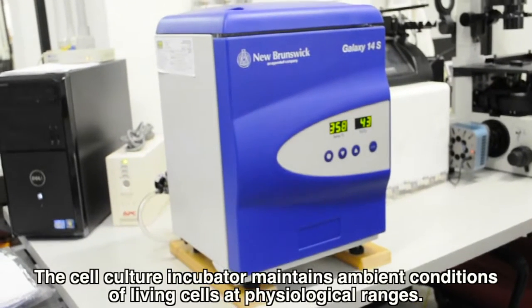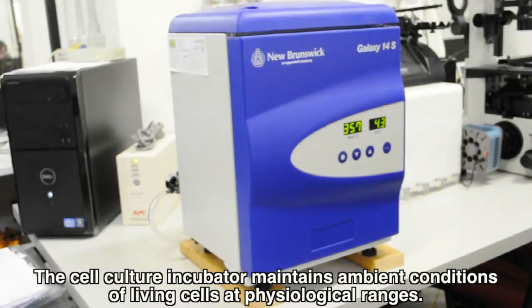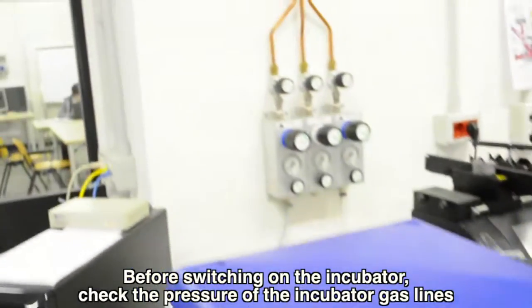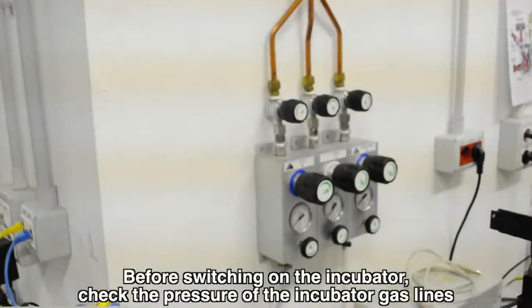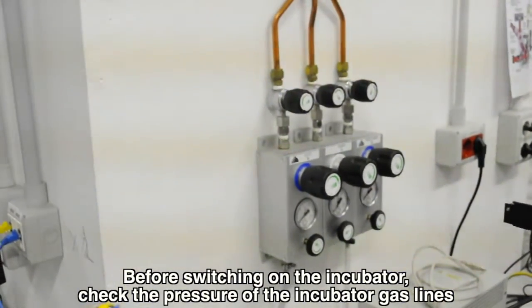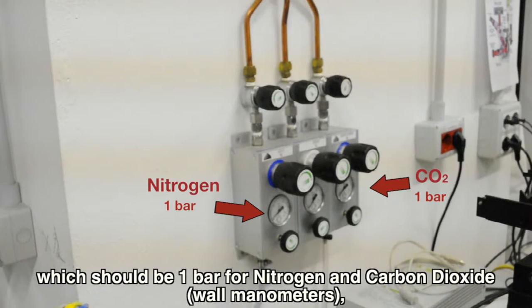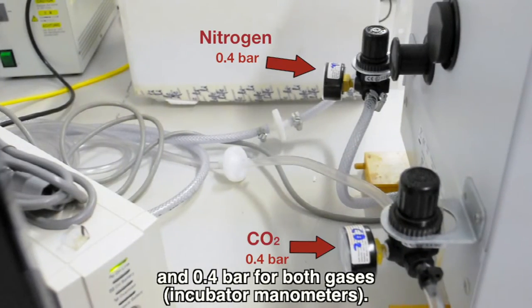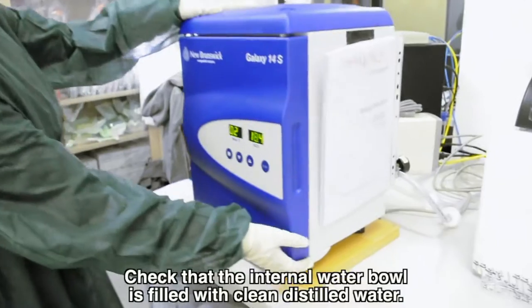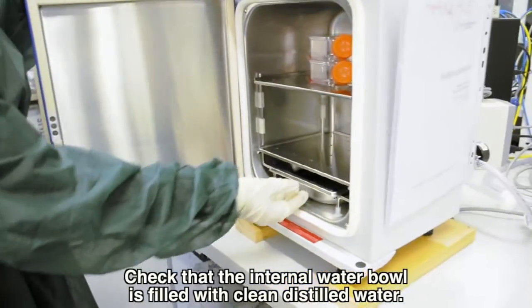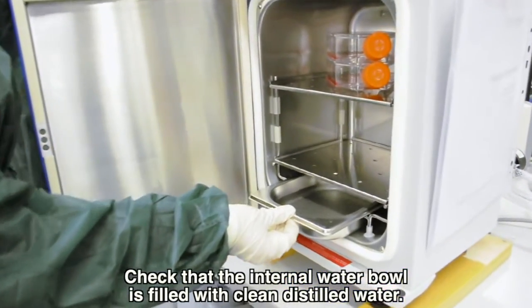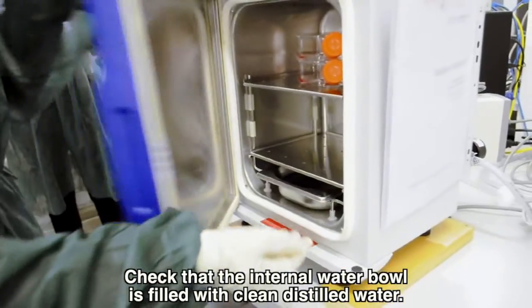The cell culture incubator maintains ambient conditions of living cells at physiological ranges. Before switching on the incubator, check the pressure of the incubator gas lines, which should be 1 bar for nitrogen and carbon dioxide wall manometers, and 0.4 bar for both gases incubator manometers. Check that the internal water bowl is filled with clean distilled water.